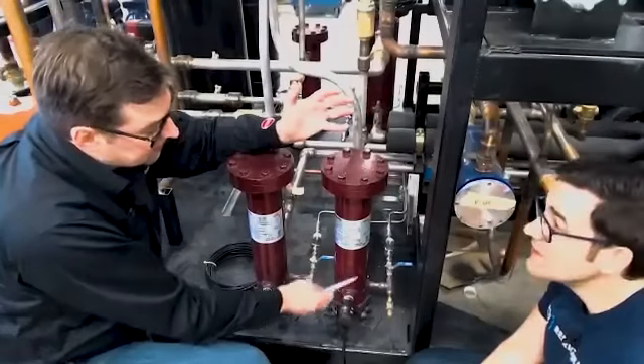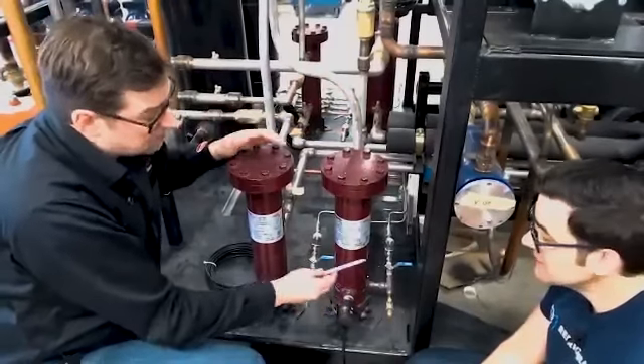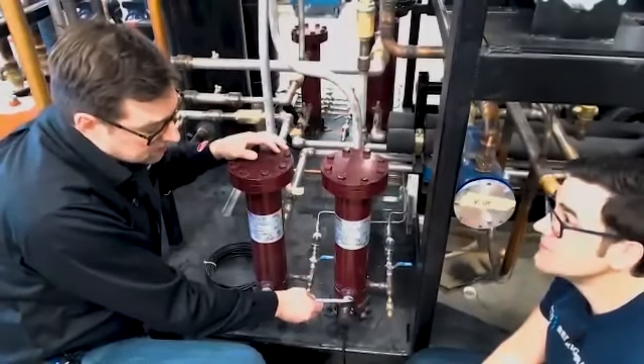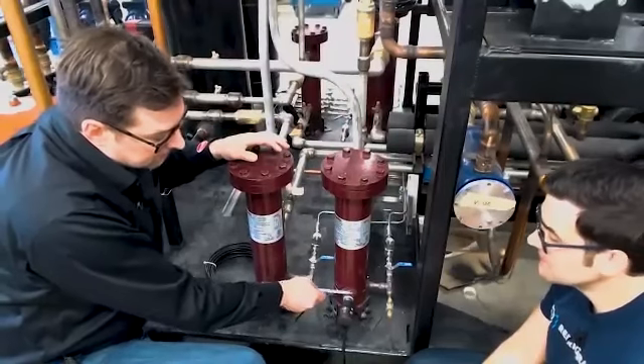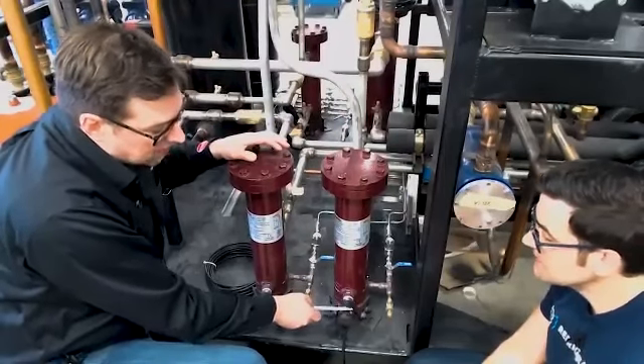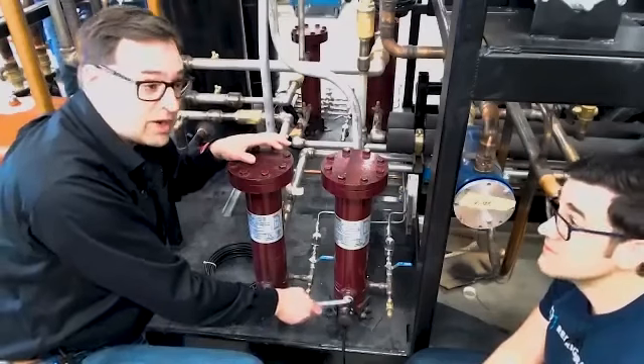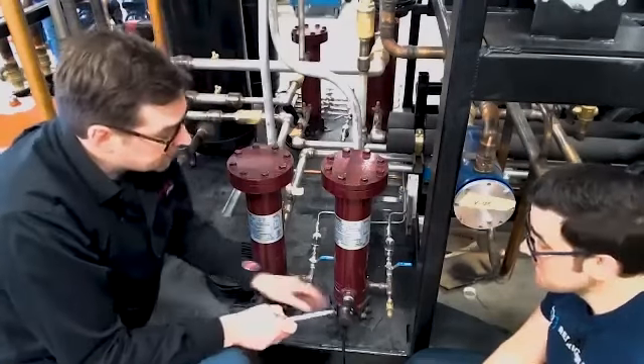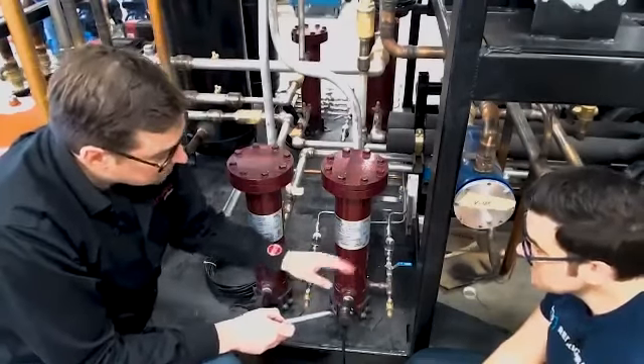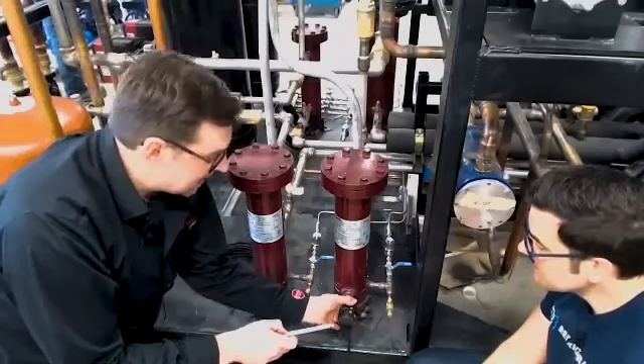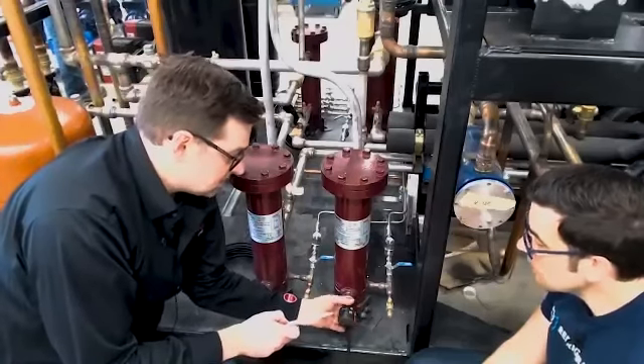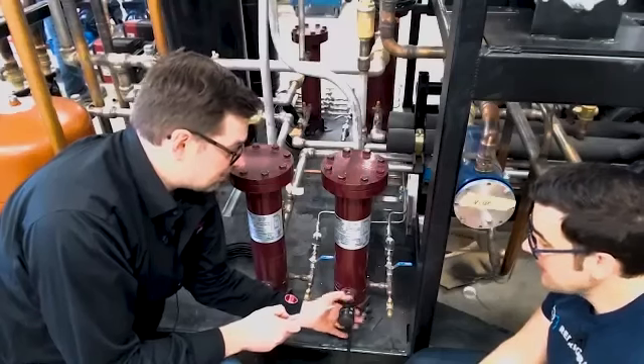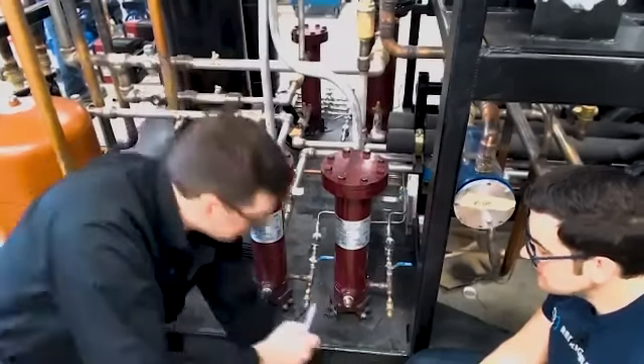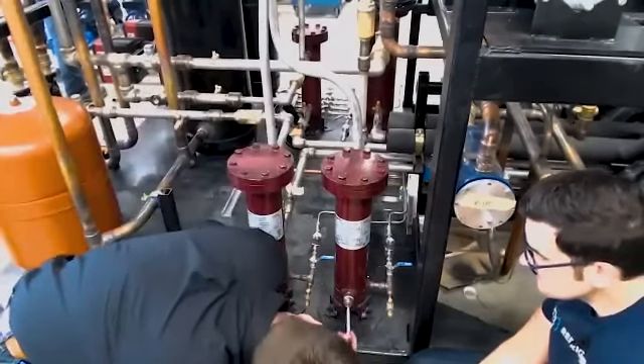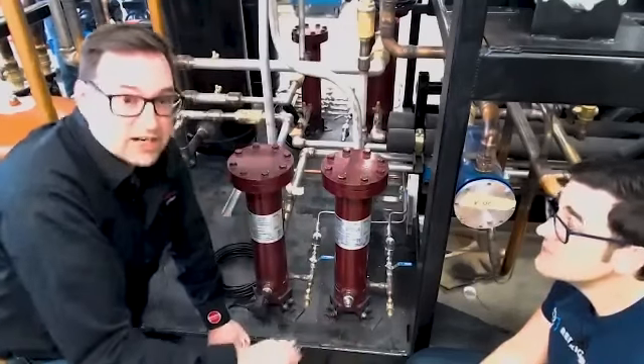Leaving this type of debris in here is potentially problematic, because it could stop the photo eye from properly sensing the oil level, okay? And another thing to check when you do your first oil change is your sight glass. You screw them right off. It's not going to let out any pressure or whatnot. You have a sealed sight glass inside here. Ensure that your sight glass is clear.